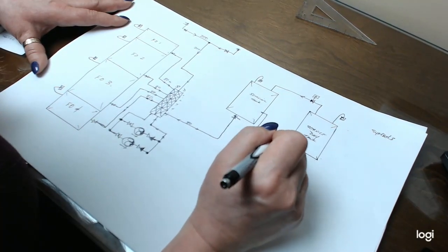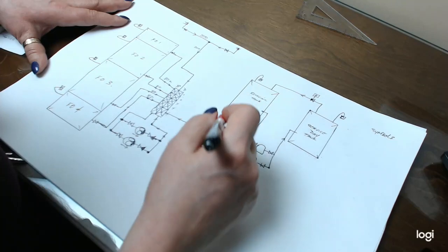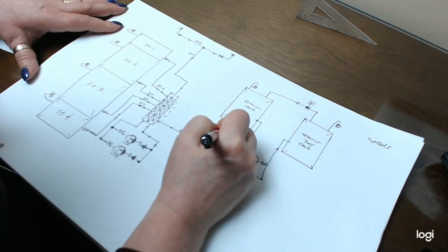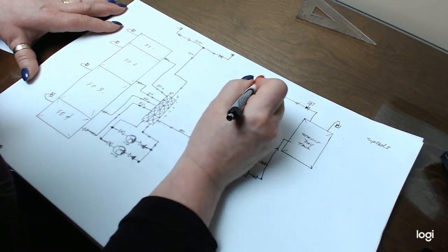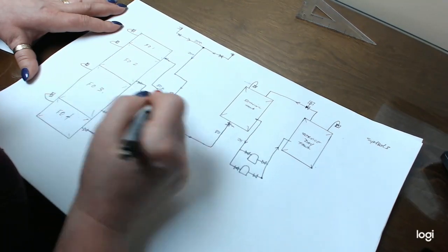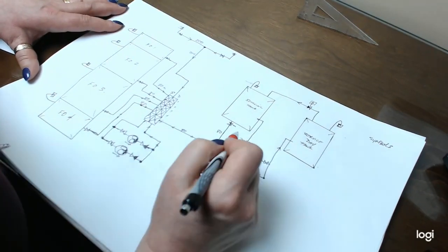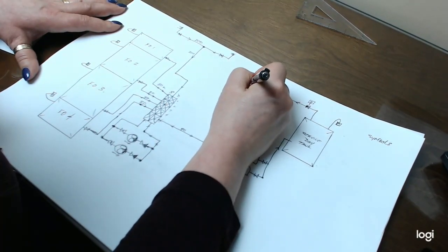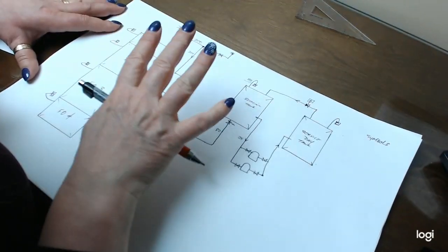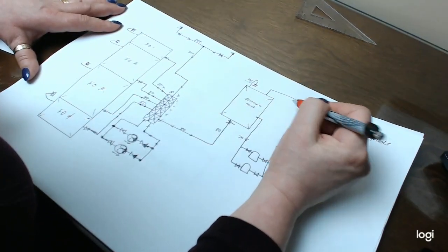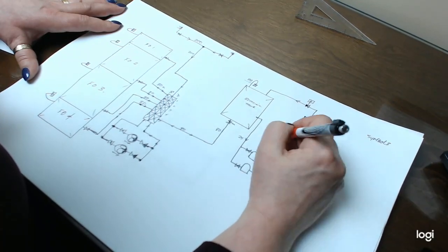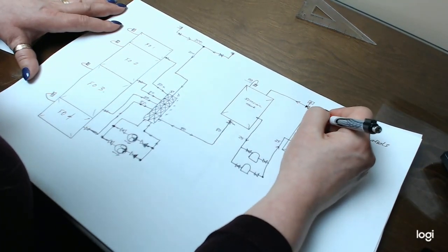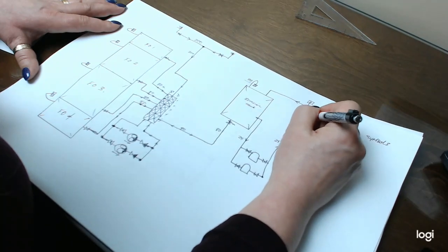But one of the things you do have to take into consideration is the pipes going in, and we'll look at the settling tank specifically. So if this pipe was going in at 80 millimeters, this air pipe has to be larger. And the air pipe is normally one pipe size up. It's actually supposed to be 25% of the area. So in this case, this vent would actually be a 100 millimeter pipe. So the air pipes are always bigger. Normally, the overflow pipes are bigger as well. So if I had, let's just say, a 25 going in here, then this one would probably be 40 or bigger, and I should put that on the other side.